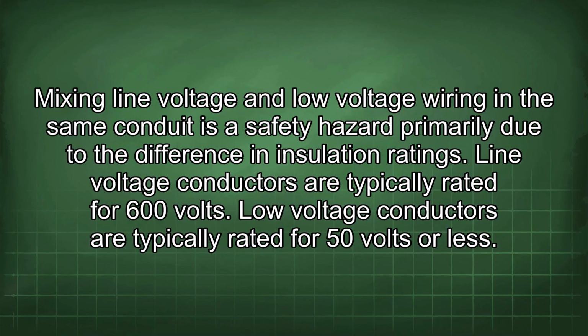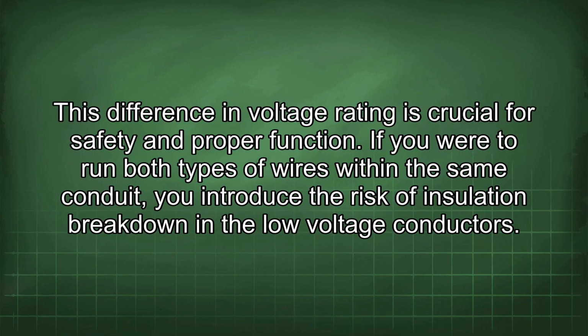Mixing line voltage and low voltage wiring in the same conduit is a safety hazard primarily due to the difference in insulation ratings. Line voltage conductors are typically rated for 600 volts. Low voltage conductors are typically rated for 50 volts or less. This difference in voltage rating is crucial for safety and proper function. If you were to run both types of wires within the same conduit, you introduce the risk of insulation breakdown in the low voltage conductors.